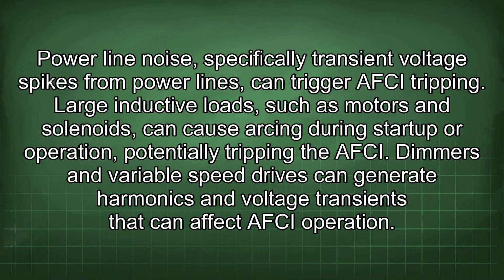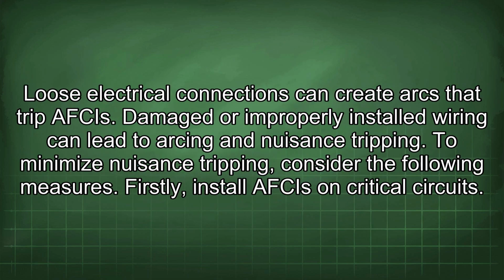Large inductive loads, such as motors and solenoids, can cause arcing during startup or operation, potentially tripping the AFCI. Dimmers and variable speed drives can generate harmonics and voltage transients that can affect AFCI operation. Loose electrical connections can create arcs that trip AFCIs. Damaged or improperly installed wiring can lead to arcing and nuisance tripping.